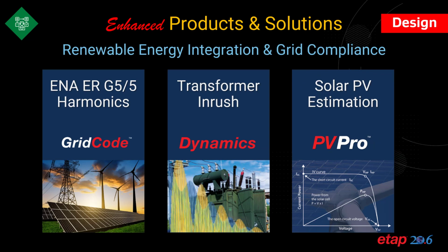ETAP 20.6 continues its enhancements for renewable energy integration and grid compliance. At the forefront is ETAP GridCode, which now allows for ENA EREC G5/5 based harmonic grid code compliance. Transformer Inrush allows for not only transformer inrush simulation, but is also capable of providing deliverables that are intended for grid code compliance. Solar PV estimation allows us to model any type of solar panel directly in ETAP, and we continue to improve and add new solar panels directly into the ETAP library.